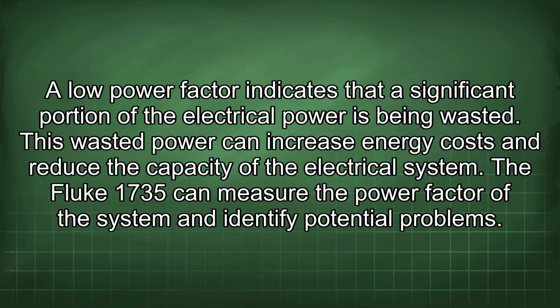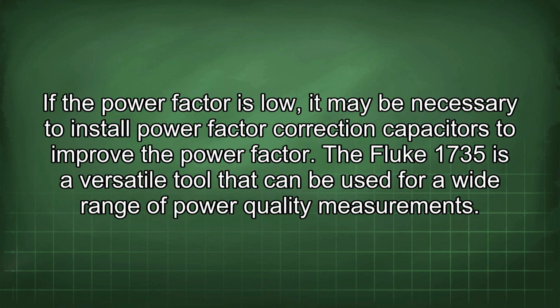This wasted power can increase energy costs and reduce the capacity of the electrical system. The Fluke 1735 can measure the power factor of the system and identify potential problems. If the power factor is low, it may be necessary to install power factor correction capacitors to improve the power factor. The Fluke 1735 is a versatile tool that can be used for a wide range of power quality measurements.